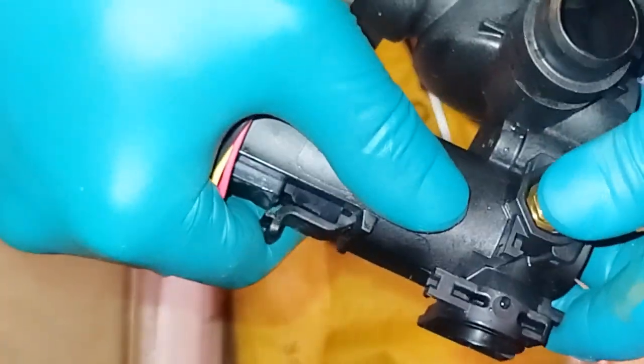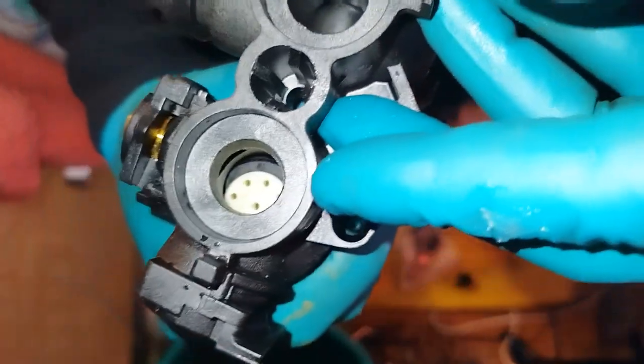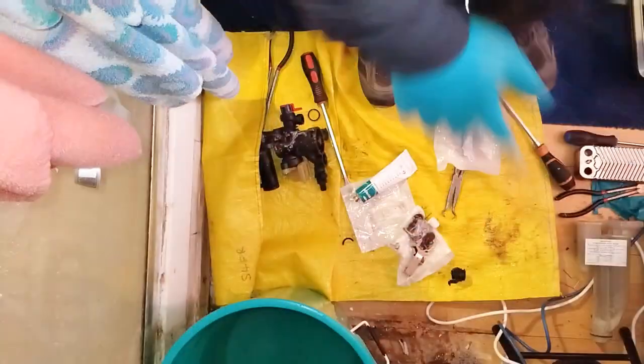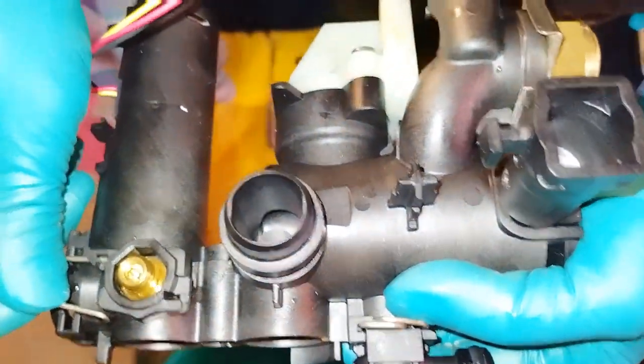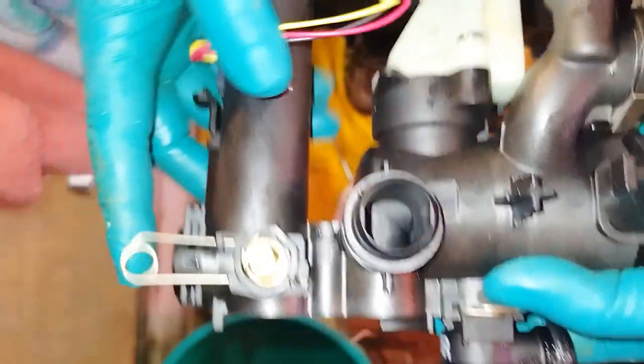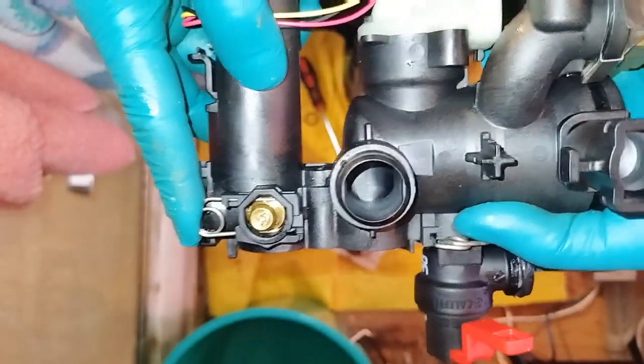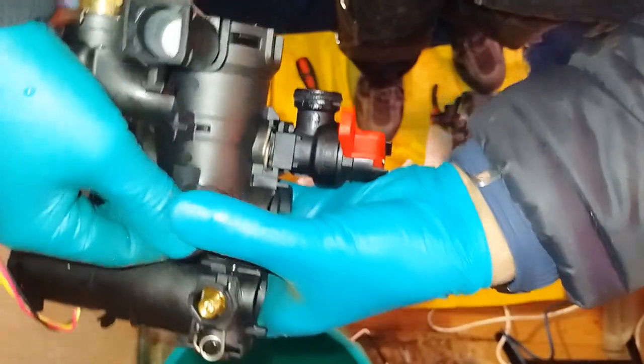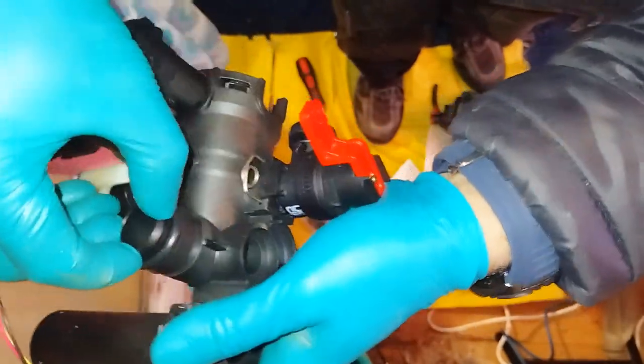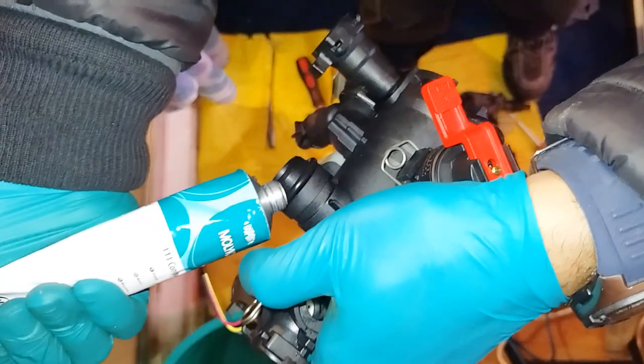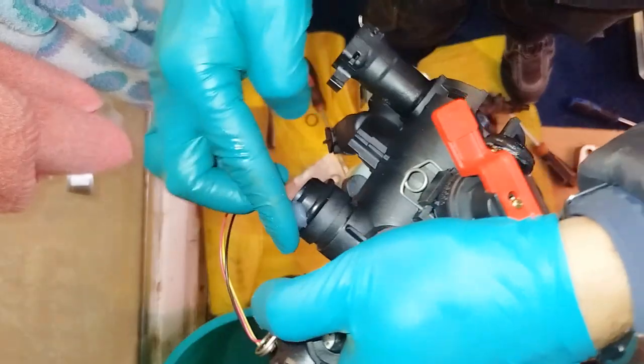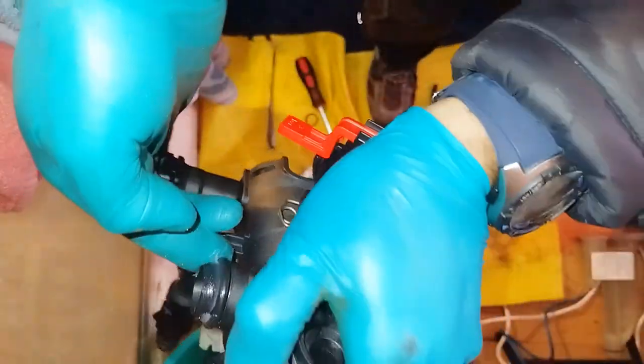If it's well lubricated, ideally with silicone grease, it will go in very easily. Okay, and there is another clip which will hold this in place. This is a relatively smaller clip, and this is how the clip goes in. Again, a locking mechanism which is on the lower side of it. And now this is the new O-ring, a big old O-ring which sits where the pump goes onto this manifold, which we put in always. Wherever you put O-rings, new ones or old ones, always lubricate them with silicone, non-setting silicone grease.